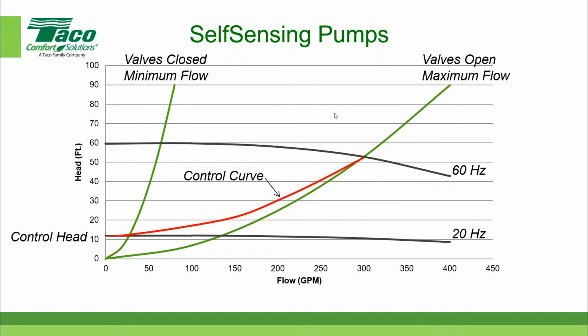And all we need to know to plot that curve is the design operating point out here and where it intersects the y-axis, called the control head, back here. And you can think of the control head as the minimum pressure required to maintain flow at the most remote point in the system.